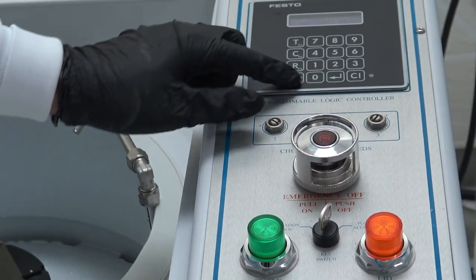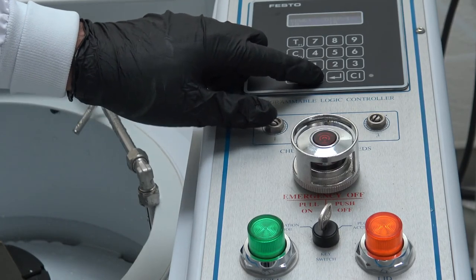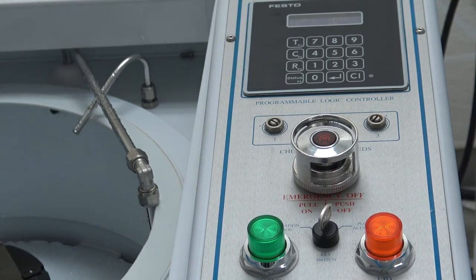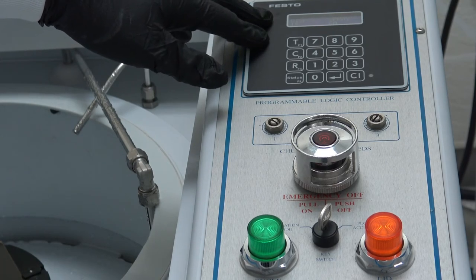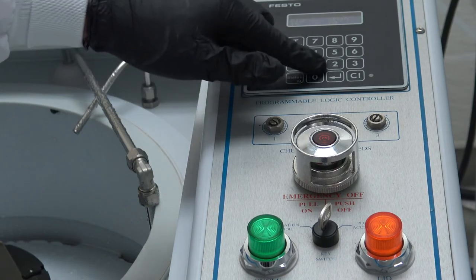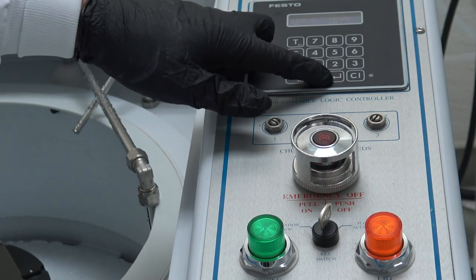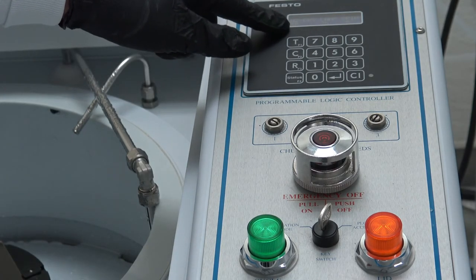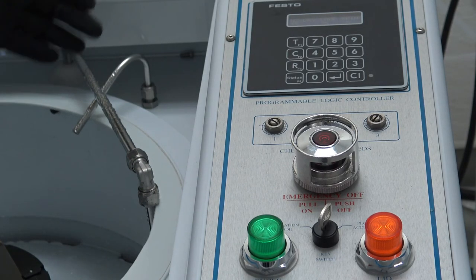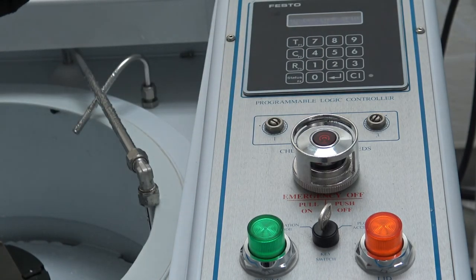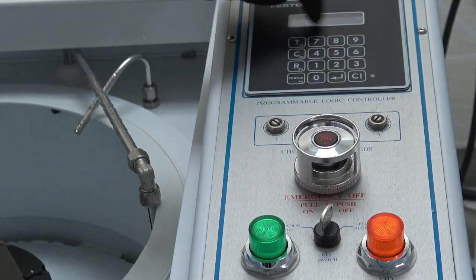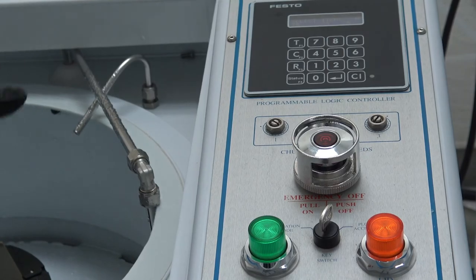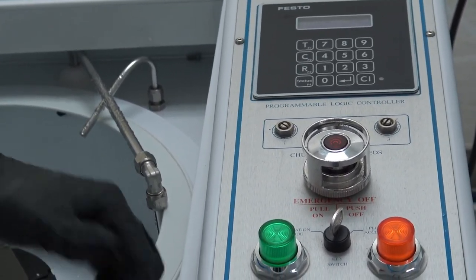Recipe edit, enter. Pre-wet, we'll do 10 seconds. Enter. Dispense 1, we'll do 5 seconds. Enter. Dispense 2. Dispense 2 is the amount of time for water to rinse or to flow from the brush scrub. That water is going to mix with the surfactant that has just dispensed prior with the 5-second dispense. So dispense 2, let's say we want to do a 20-second rinse and scrub there. A 60-second high-pressure spray. Let's adjust it to 55 for purposes of demonstration. Here we have the N2 dry. That's how long the N2 is going to be blowing out of the nozzle for drying. We then have the lamp, which is how long the heat lamp is going to be on after the N2 dry. And then we have just a spin-down setting for the amount of time that the wafer is just going to spin with neither on. You typically aren't going to have a very long spin setting. It's mostly going to be through N2 dry and heat lamp that most of your drying comes.